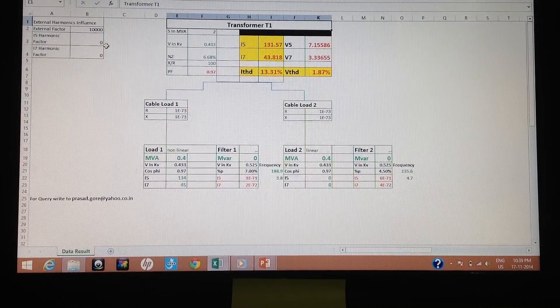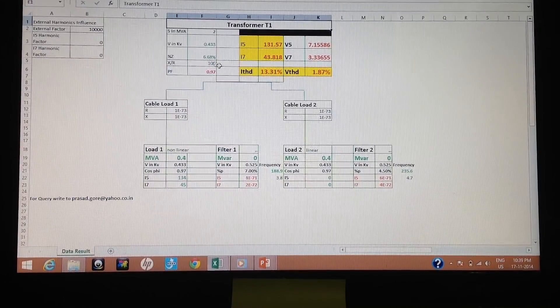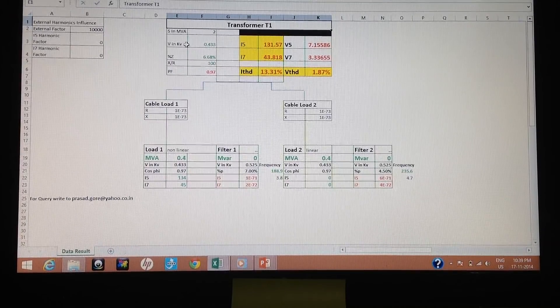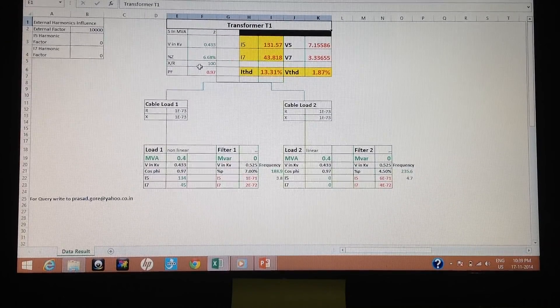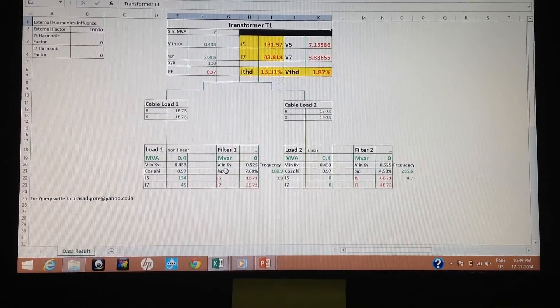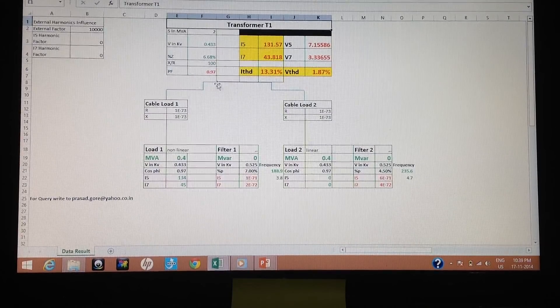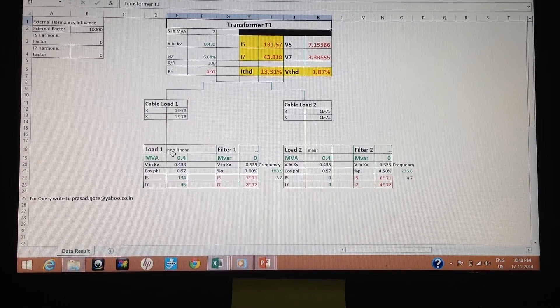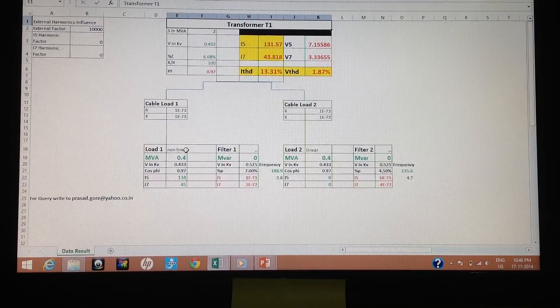Now we will see the transformer and load details. The transformer is 2 MVA, 0.433 KV voltage, 6.68% impedance, X/R ratio of 100, and power factor of 0.97 depending on load. There are two load centers: load center 1 and load center 2. Load center 1 has a 0.4 MVA load at a power factor of 0.97.